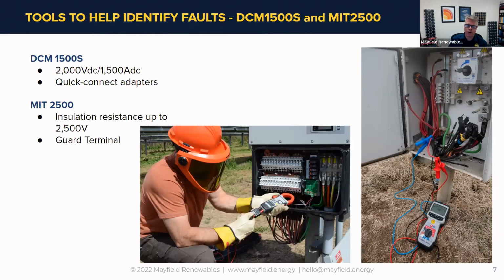And I should preface that with the expectation that you are not doing this through the modules themselves. I know people do insulation resistance testing through the modules, but I have yet to get that okay from the module manufacturers. That's one of the things you should be doing if you're going to do it. Some people have gone that extra distance, some people don't. So back to the destructive element, Mike, if we're doing these tests, should we be concerned? Are we degrading our conductors faster by doing these tests?